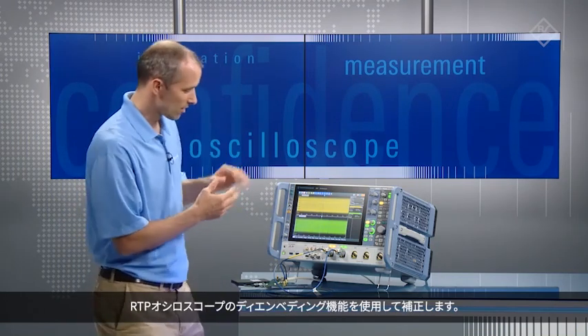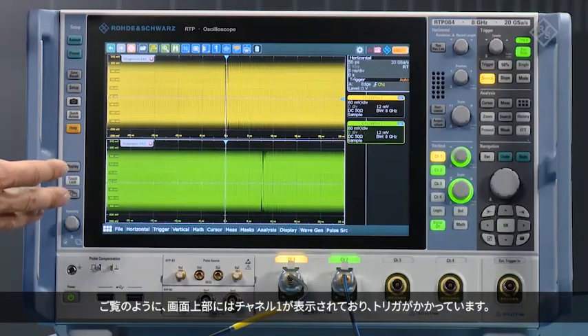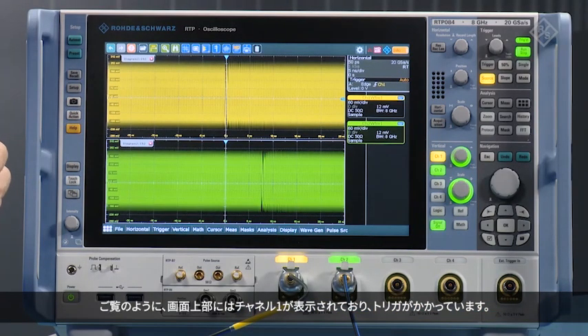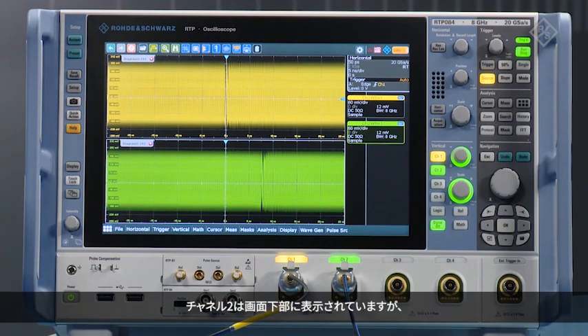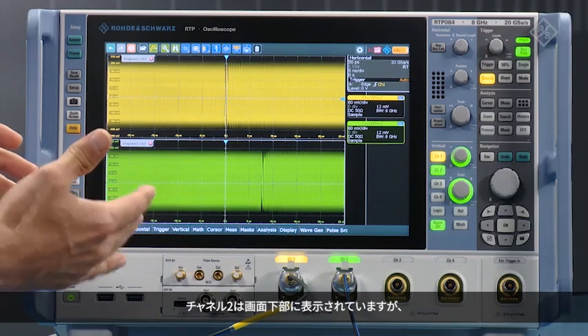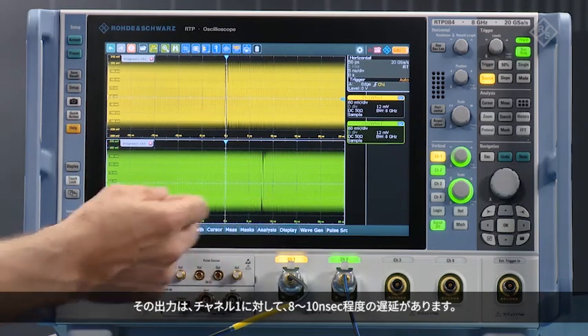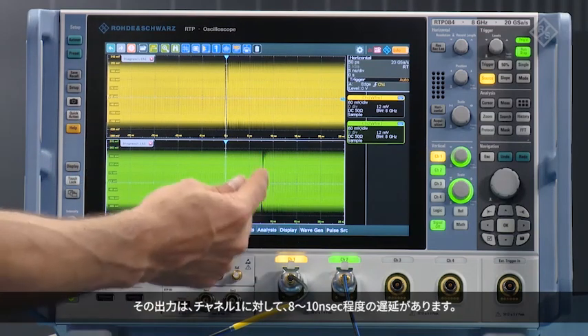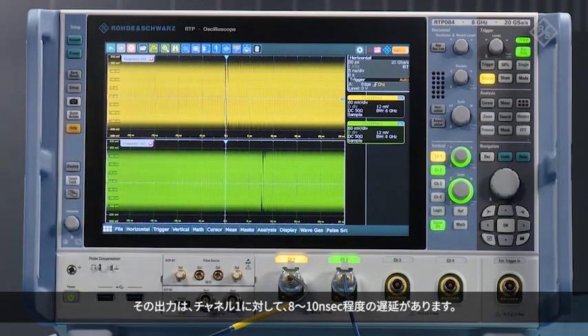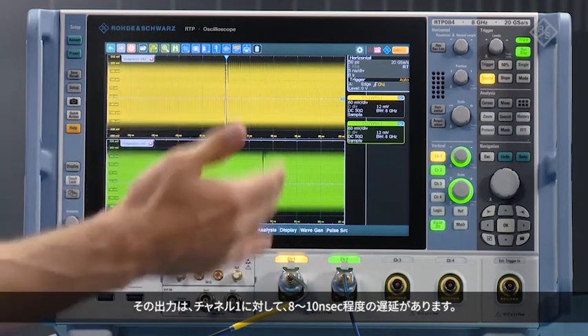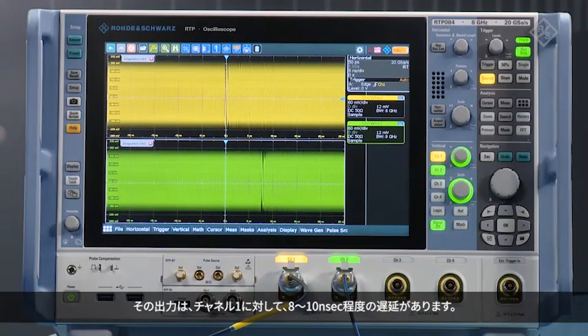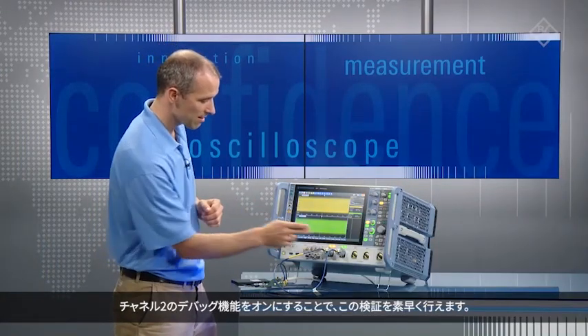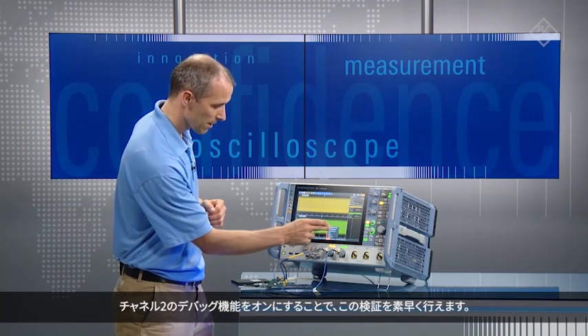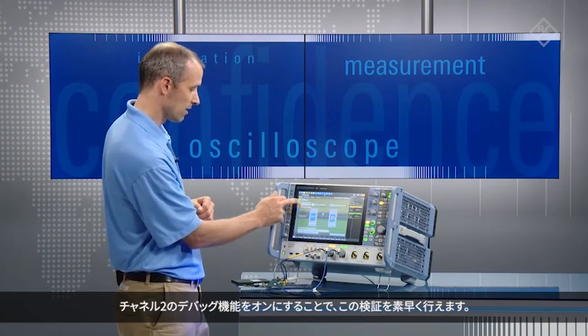oscilloscope. So as you can see on the screen here, we have channel 1 up top, which we're triggering on. Channel 2 is also displayed on the bottom, but we can tell that there's some 8 to 10 nanosecond delay between the output of channel 2 and channel 1.